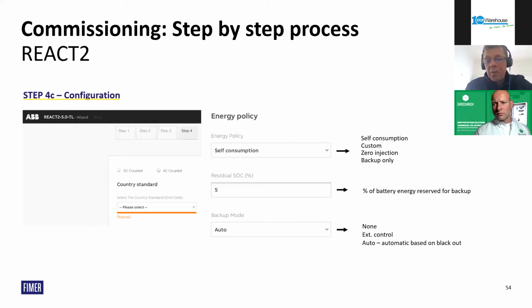If you have an energy meter connected, you can configure it to self-consumption, zero injection if you have zero export, custom if you have any export limitation, and there's a backup only option, which I've never seen used in Australia - that's just giving priority to the battery.